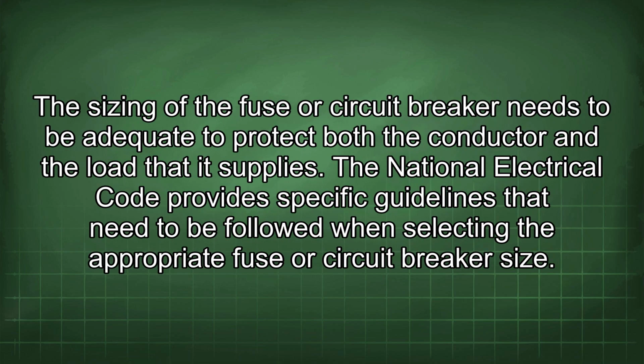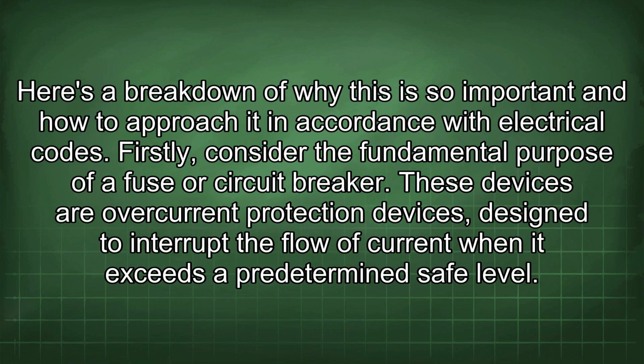The sizing of the fuse or circuit breaker needs to be adequate to protect both the conductor and the load that it supplies. The National Electrical Code provides specific guidelines that need to be followed when selecting the appropriate fuse or circuit breaker size. Here's a breakdown of why this is so important and how to approach it in accordance with electrical codes. Firstly, consider the fundamental purpose of a fuse or circuit breaker.